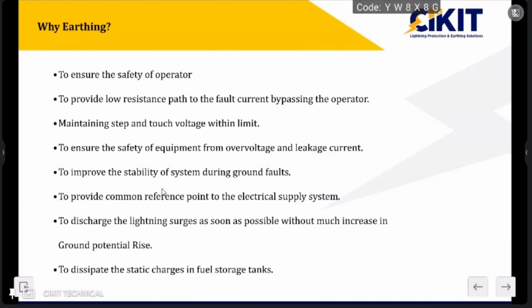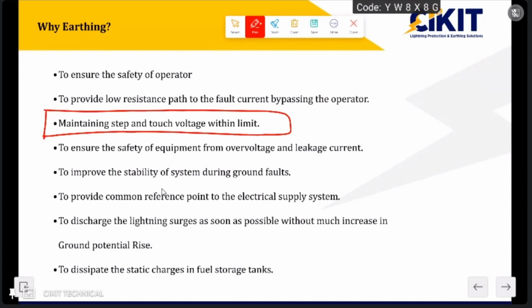The ultimate aim of providing earthing is the safety of the operator. For any equipment in industries, if a person makes contact with equipment which becomes live, he will get electrocuted. But the problem with a substation is that even without direct contact, a person working inside the substation may get electrocuted. So in substations, the ultimate aim of earthing is to maintain the step and touch voltages within the limit. For touch voltage you have to make contact, but for step voltage no direct contact is required.